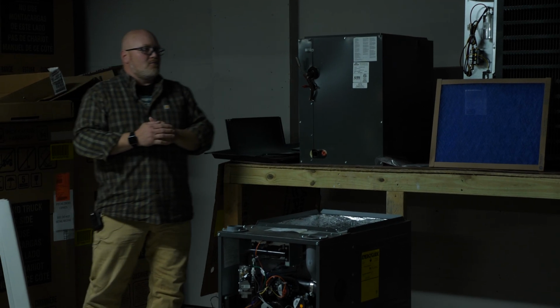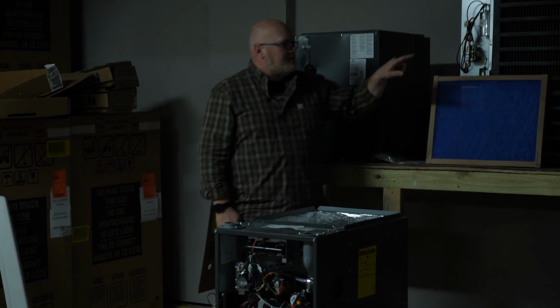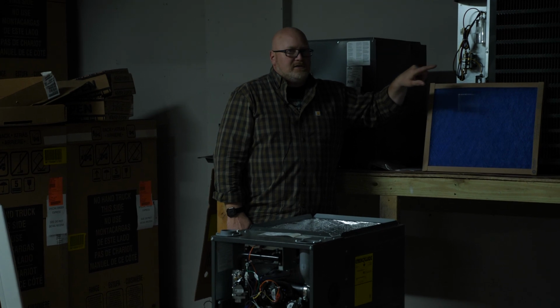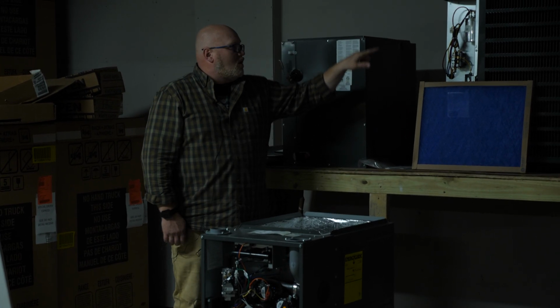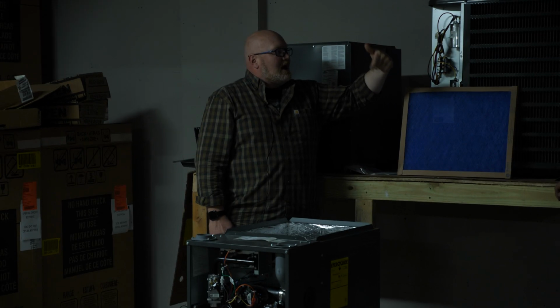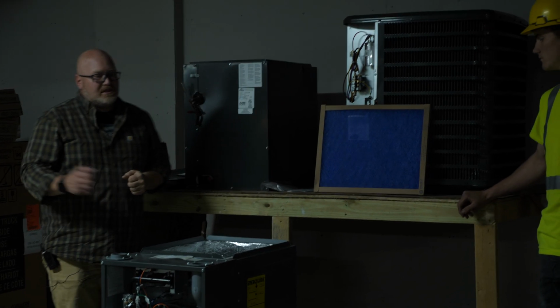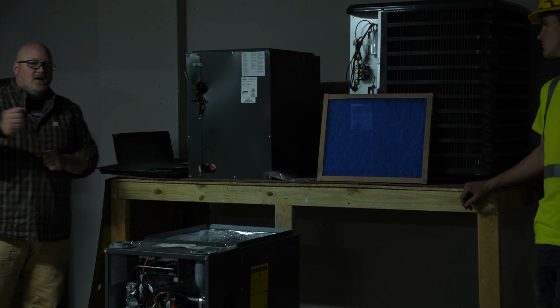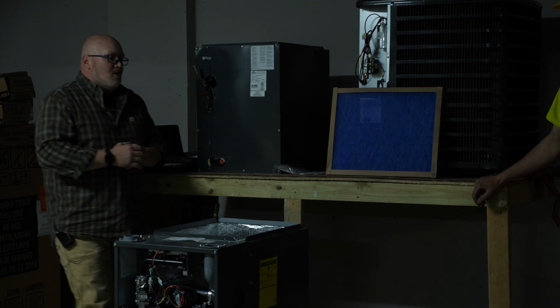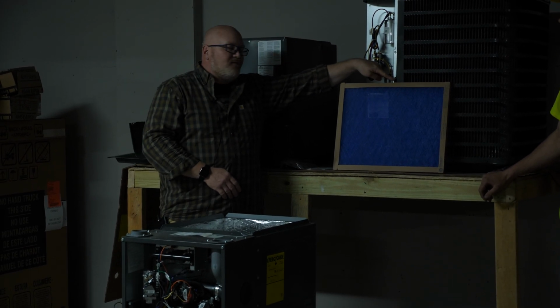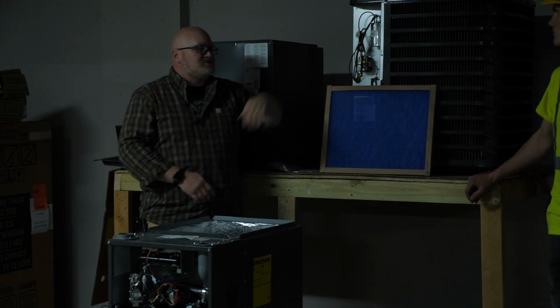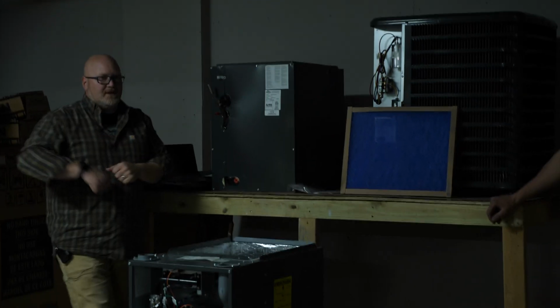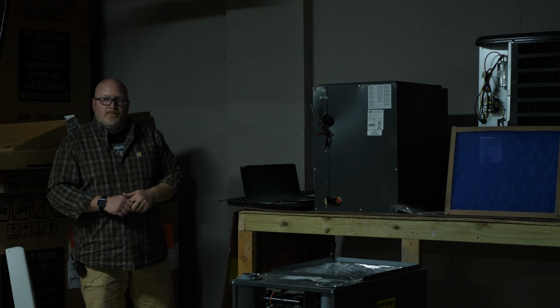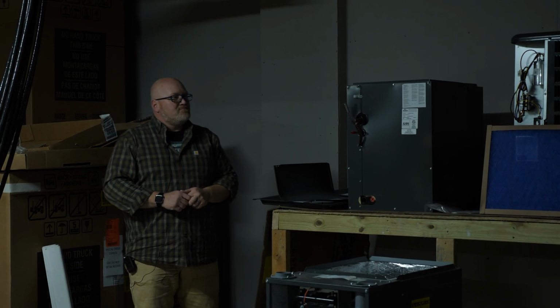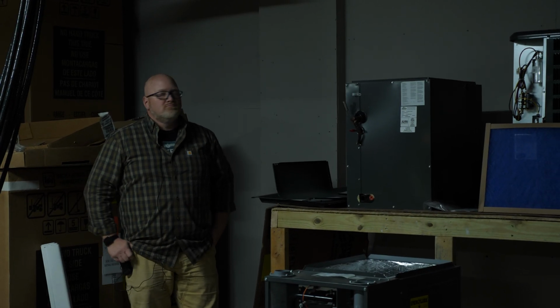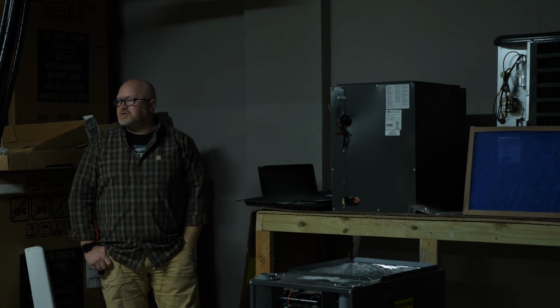I want to be very clear. What we don't want to do is drive the dirt, the cottonseed, into the coil. We want to drive it from the inside out. So getting a hose, getting a sprayer, and spraying around will do magic, will do miracles. Or if you're so inclined, you could pull the 5/16 screws on the cage that covers it. You could take a dry brush. You could get all that stuff out of there. Straight from the inside out, you have to pull the top off, the fan off, and just spray it. You could use air too, yeah.